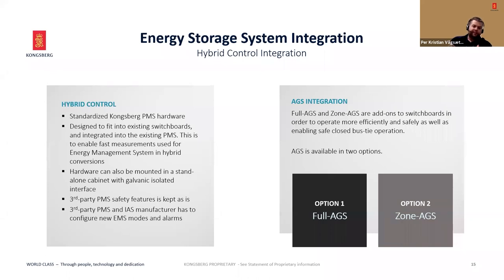The energy management system allows us to gain further beneficial features in battery utilization on board. By talking to our DP system, we can predict incoming forces and prepare the power management system to select whether the battery takes the load or the engines ramp up. We also have what we call a zone AGS, based on the same standardized PMS hardware, which allows the existing switchboard to be reclassified into closed bus-tie operation, enabling the highest potential fuel savings as well as reduction in running hours.